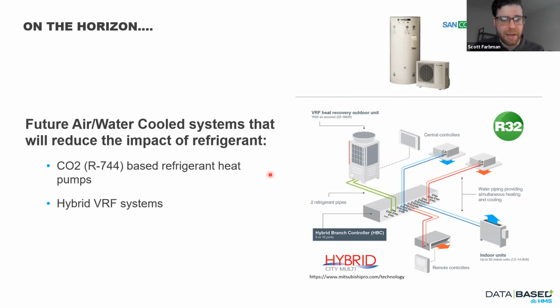Something else that's supposedly coming by the end of the year from Mitsubishi is called a hybrid VRF. These are being designed and installed outside of the US, in the UK, Australia, and New Zealand, but they're not offered here yet. And what this system does is actually quite great. So there's still refrigerant, but they've limited the run of refrigerant from the outdoor unit to an indoor branch controller. From there, things get converted into a hydronic system where hot or chilled water is then distributed throughout the entire building. So that refrigerant boundary that I showed a couple slides back is minimized closer to what a package unit might look like. So there's less refrigerant charge, and less opportunity for leakage because you don't have all those fittings and connections and field installed lines throughout the entire building.